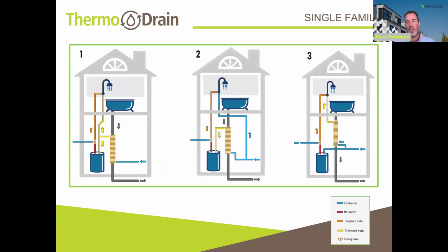Drain water heat recovery units can be installed in a few ways. You would have it installed on the main drain stack. So this is what we were looking at earlier. We have a main drain stack on which the unit is installed. The preheated water comes out and goes and feeds a hot water heating device. Alternatively, we can do something similar to this one, where the preheated water goes and feeds the cold side of a fixture. These two scenarios basically have similar efficiencies. They perform similarly, but maybe the layout of the house makes number 3 here more practical in the plumbing of the preheated lines versus perhaps number 2.